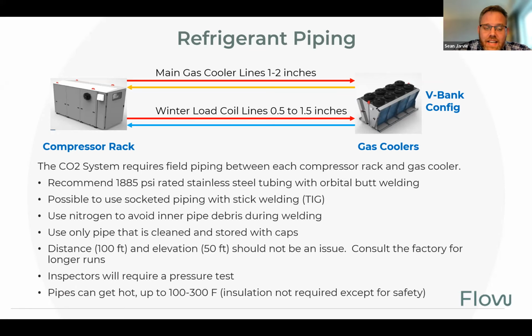Right out of the gate, they are set up to run 100 feet and up to 50 feet of elevation change. Our record holder, done by our CEO personally, has gone 1,000 feet and about 200 feet of elevation change. He's quite proud of himself on that installation. But it's the power of CO2 as a refrigerant that can do that. It's volumetrically much more efficient than any other refrigerant out there. And because we are guaranteeing a solid column of liquid, we can do things like this, which is really cool.